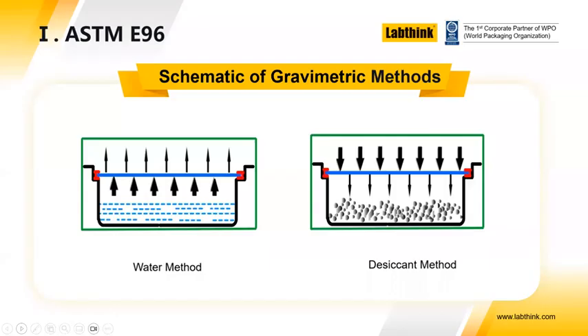Sample forms the lid, and the direction of permeation is from the outside to the inside. And so in one method, as the procedure progresses, the weight of the cup decreases because the water evaporates, the water vapor passes through the specimen, and it goes out into the environment of the chamber. And so over time, the amount of water in the cup will reduce, the weight of the cup assembly with the specimen decreases. And so we're looking at measuring a weight decrease.